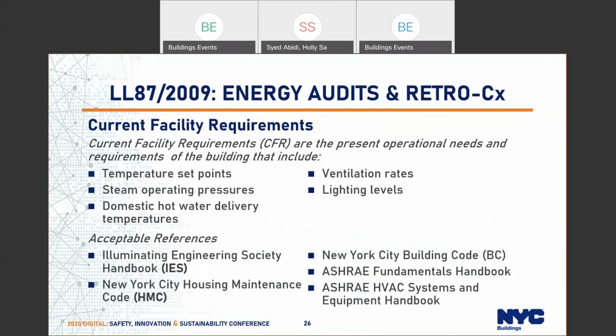There was a clarity needed for defining the current facility requirements that is addressed by the rule amendments. Current facility requirements are the present operational needs and requirements of the building that include temperature set points, steam operating pressure, domestic hot water delivery temperatures, ventilation rates, and lighting levels. Current facility requirement establishes the success criteria of the retro-commissioning exercise. It must be justified by acceptable references that include IES, HMC, which is New York City Housing Maintenance Code, Building Code, ASHRAE Fundamental Handbooks, and ASHRAE HVAC Systems and Equipment Handbook.